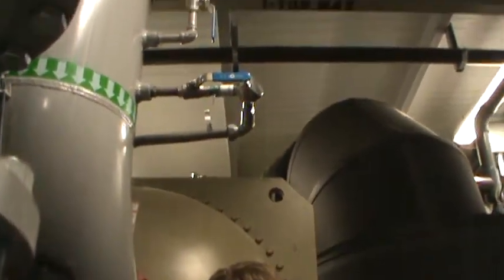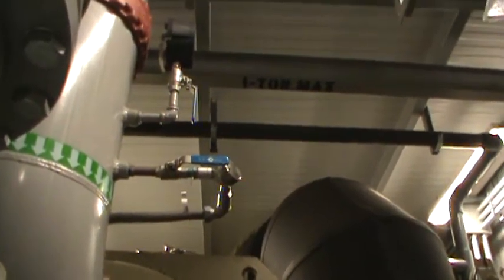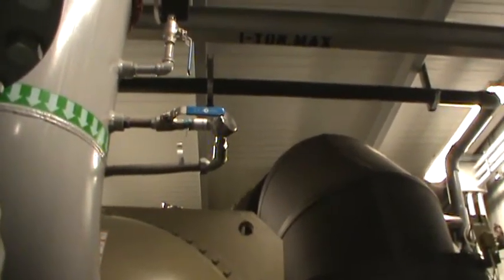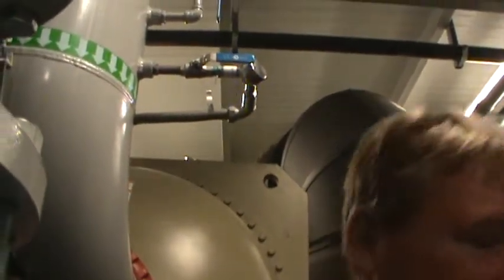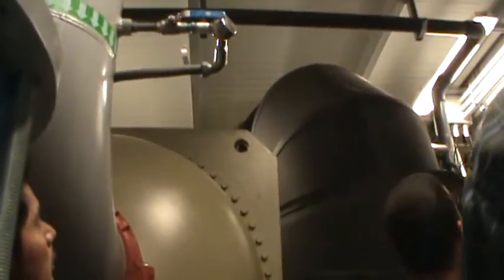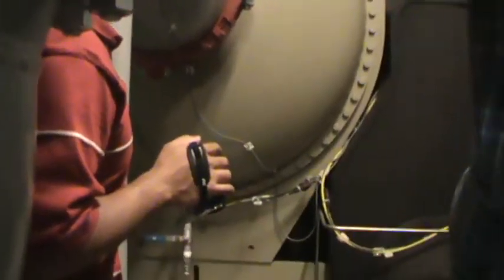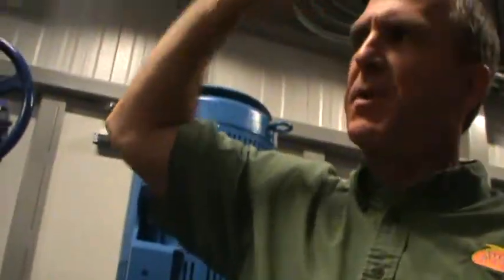So how would y'all get in to service something like that? Y'all got an area like doors on that end? That's a great question. To get to the compressor motors where the compressors are, that whole roof section back there comes off, and if you looked at the cooling tower, you saw a large space between this roof and the bottom of the cooling tower, and there's another trolley system up there. So we pull the roof off, and the beams are rated so we can rig that compressor, lift it and pull it out. It goes all the way out the end, and there are panels that come off at the very end. That's how we'll get it out onto a truck.